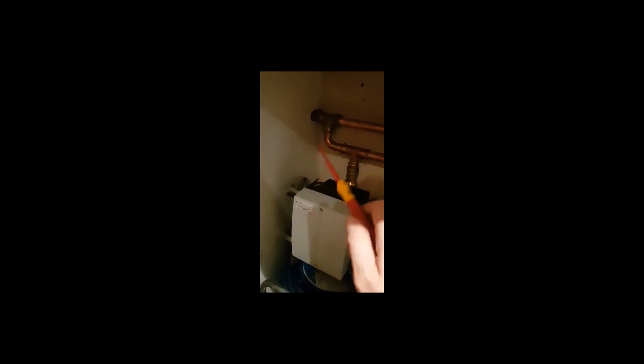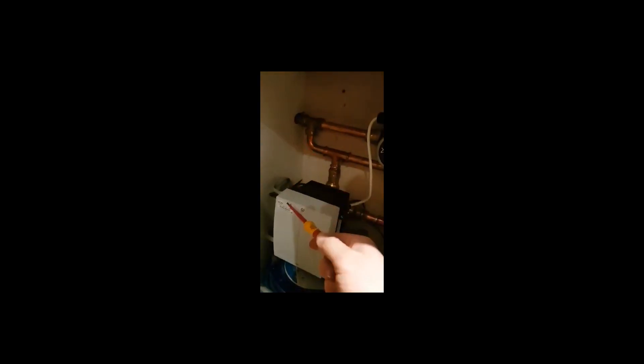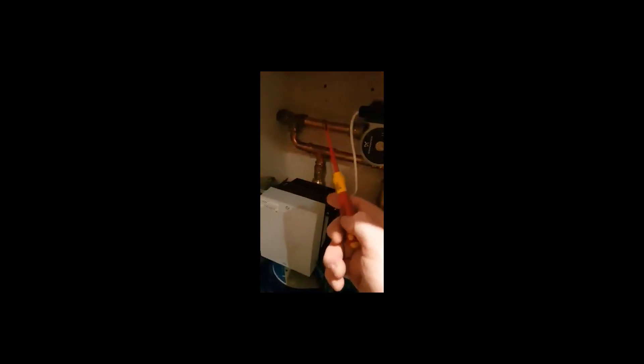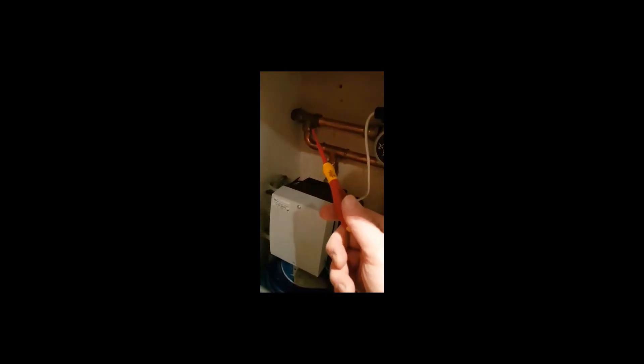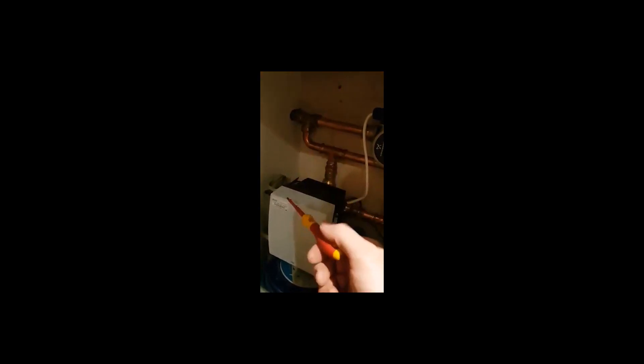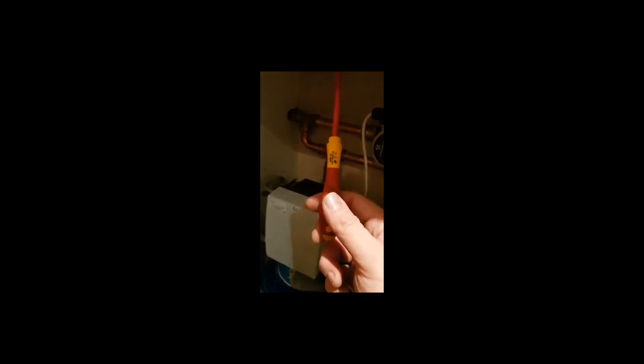So you can have Delta T20 on this side with smaller bore pipework, and Delta T10 on that side. This side is compensated for radiators, and what this also avoids is you don't have to fit a zone valve.